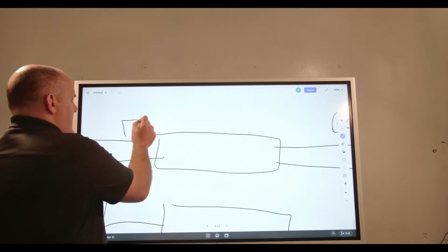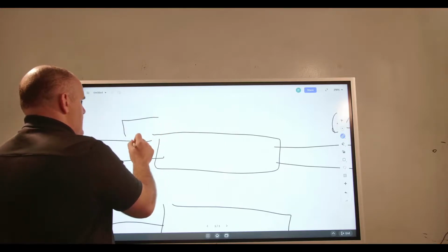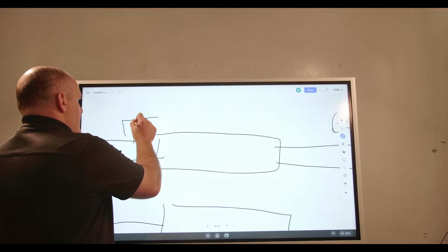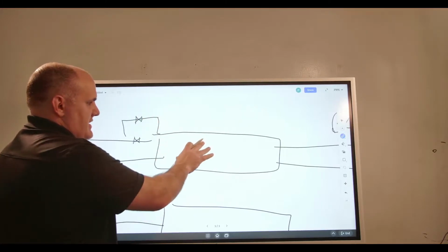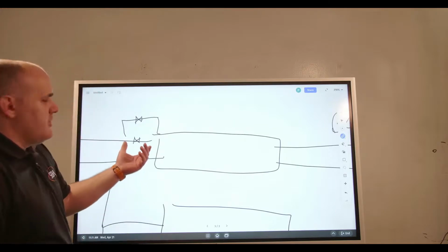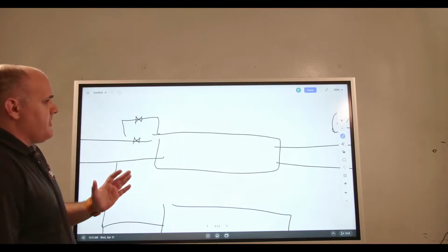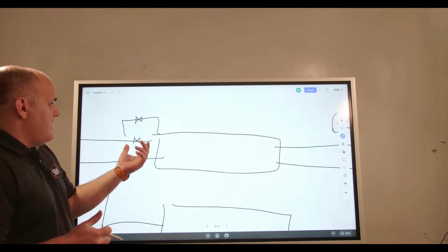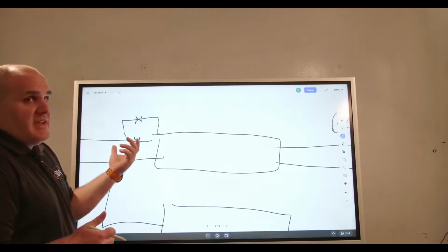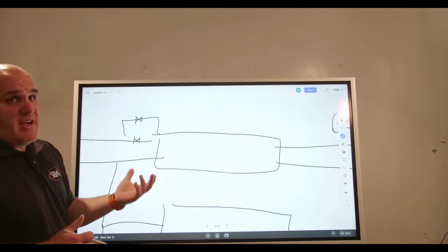It'll look more like this, where we have a 1/3 valve and a 2/3 valve going to this heat exchanger. And what we'll typically do is we'll open the 1/3 first, and that's where most of the steam is going to come through. That's why if you've ever done steam control, you'll know that within the first 30% of opening that 1/3 valve, you typically get the most shock on the process variable.